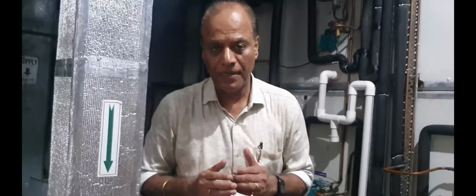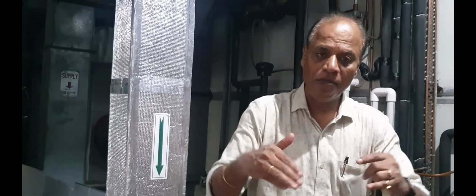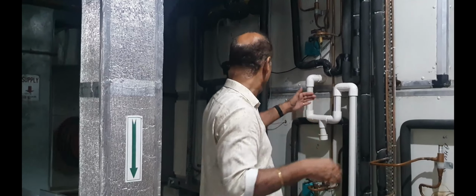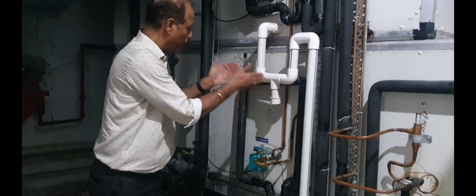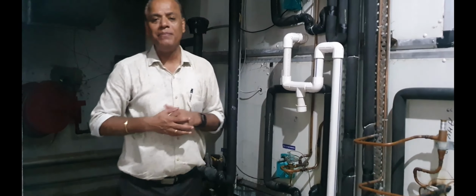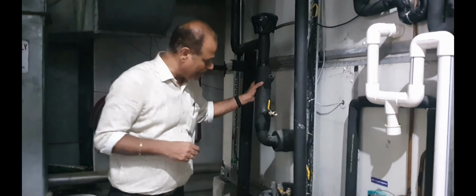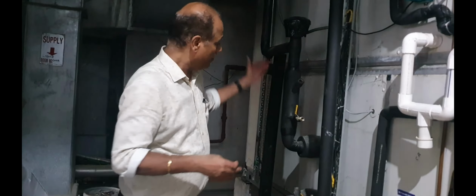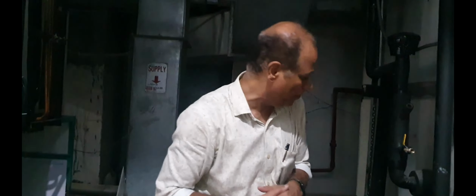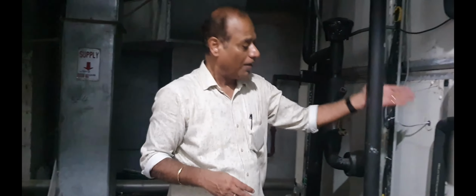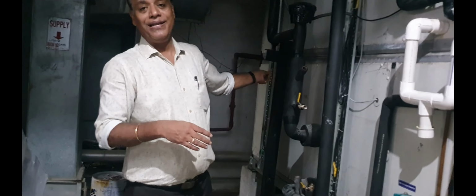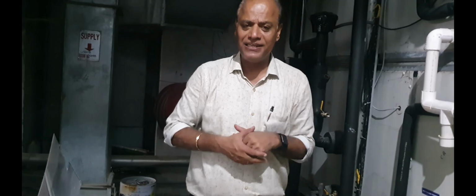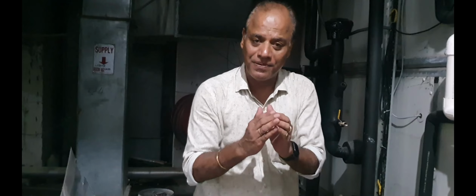In the EM series dehumidifier, the whole working is based on cooling the air, subcooling the air. In this system, this is the first cooling coil and this is the second cooling coil. In the second cooling coil, the air is cooled to about 2 or 3 degrees centigrade, whatever temperature is required as per the design. This is the hot water coil, and the hot water generated in the EM series hot water generator is circulated in all the dehumidifiers I've shown you. This hot water reheats the air from 2 or 3 degrees centigrade to 12, 13 or maybe 15 degrees centigrade, whatever the design requires. Each and every step is controlled.